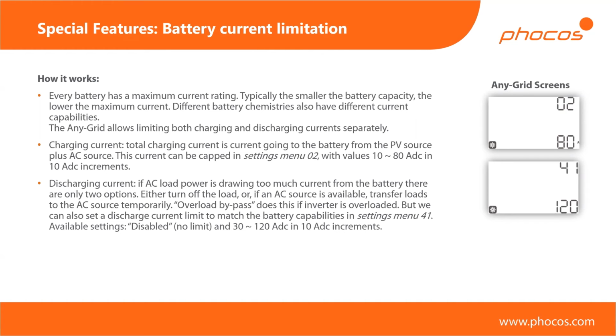Regardless of whether you've set a priority to charge from PV or from grid or from both, this is like a total cap. It will add together your charging from PV and from AC if activated, and then it will simply cap anything higher than, for example, 40 amps, to make sure that your battery is not receiving too much charging current. Too much charging current can cause several things, but two main ones. Overheating the battery is the obvious one for lead acid batteries. If you're using lithium batteries, it's worse for the system, but better for the battery.